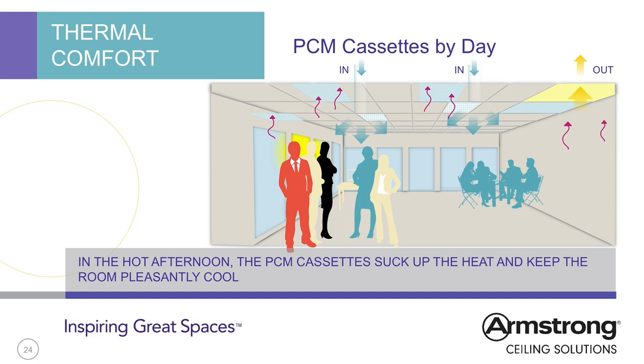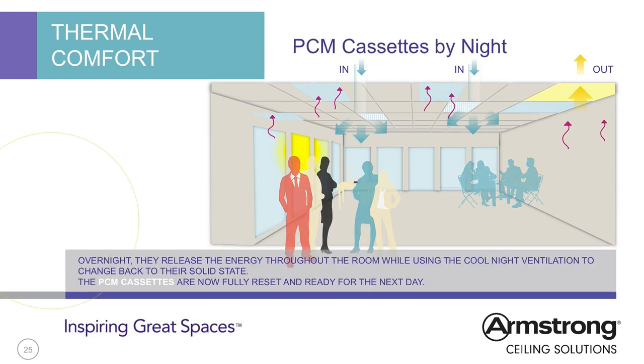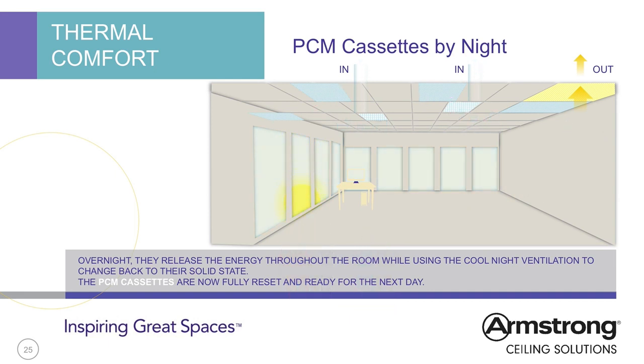PCM tiles should not be cut and are not suitable for perimeter cuts or service penetrations. The speed at which the wax melts — and thus the delay before room temperature increases — depends on the heat load produced inside the room. At the end of the working day, when the heat load is removed or reduced, the purging process begins, resetting the PCM tiles for the next day by cooling the tiles below 24°C and changing the phase from liquid back to solid. This releases the stored heat energy back into the room. The purge can be achieved by natural ventilation from cool outside air or by using lower-tariff energy costs and air conditioning.